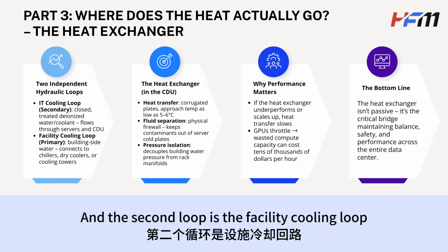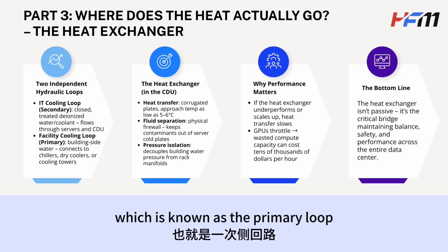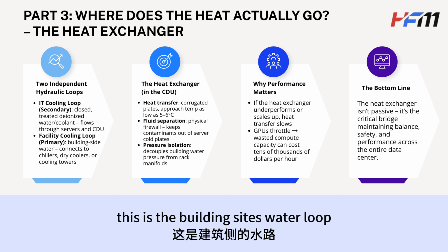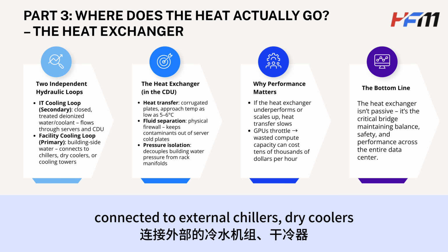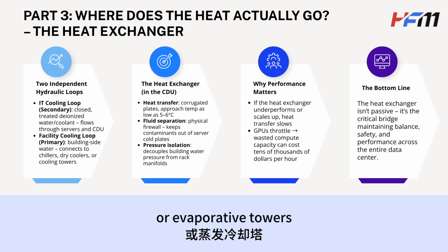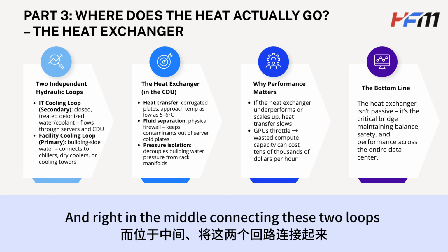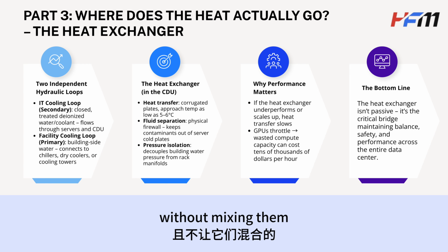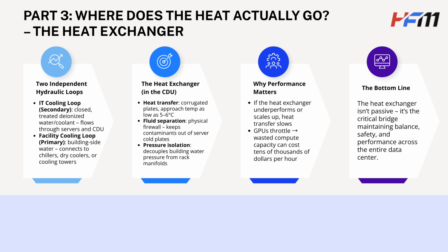The second loop is the facility cooling loop, known as the primary loop. This is the building site's water loop connected to external chillers, dry coolers, or evaporative towers. Right in the middle, connecting these 2 loops without mixing them, is the heat exchanger.